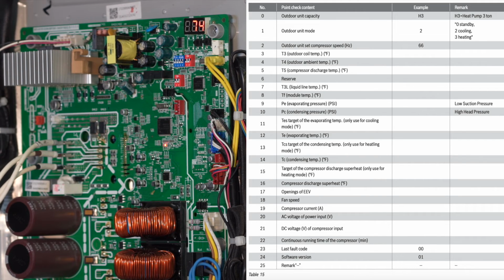So Ken, review in just a little bit. What did you get on number 7? Number 7 was 76. What was 14? 14 was 87. So 76 and 87. Do the math. 11 degrees. This machine has 11-degree subcooling. Exactly. All I have to do is basically push a button, do a little bit of simple math. Absolutely. Superheat, subcooling. What a deal. Unbelievable.